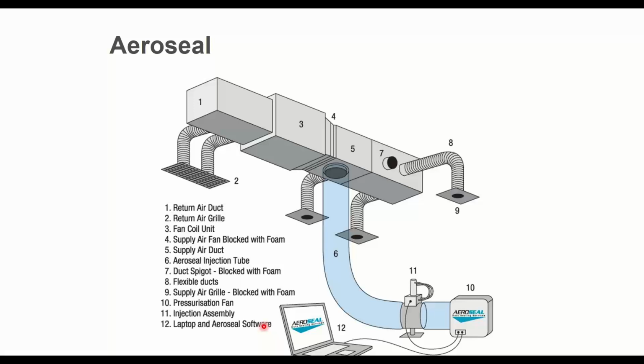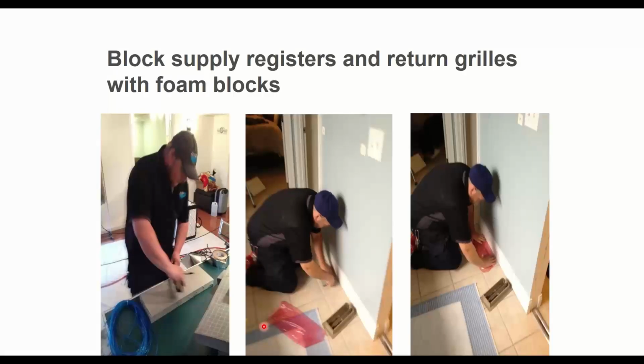So you put these foam blocks in, and let's say you had a 4x8 register, or 4x10 register. We'll cut the foam block 4.5 by 10.5 inches, a little bit bigger, so you really have to jam it down in there. And then the pressure of the diffuser, or in this case, the boot, is going to compress that foam, so really it can't go anywhere.